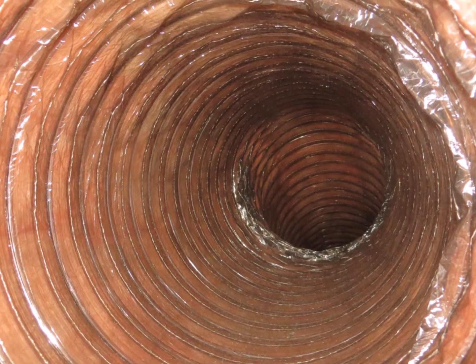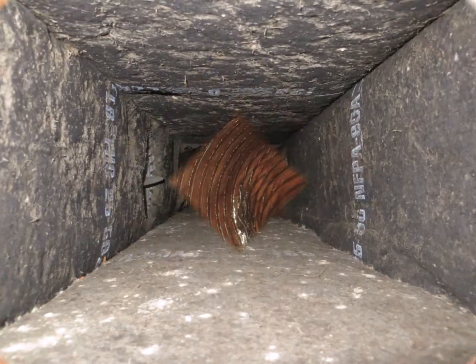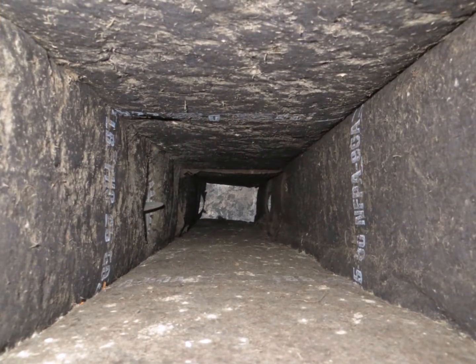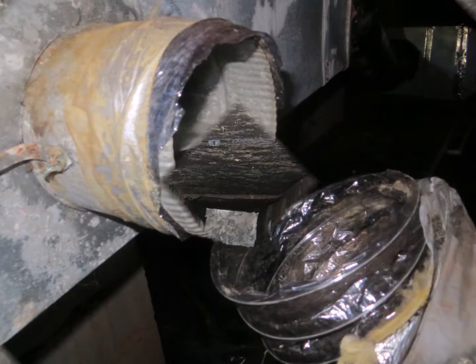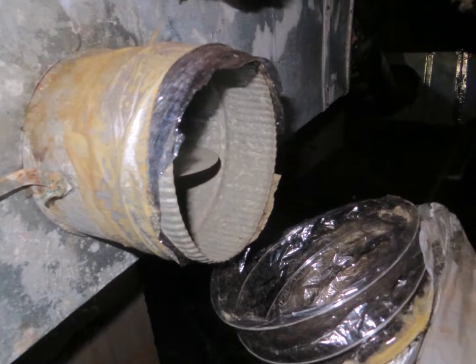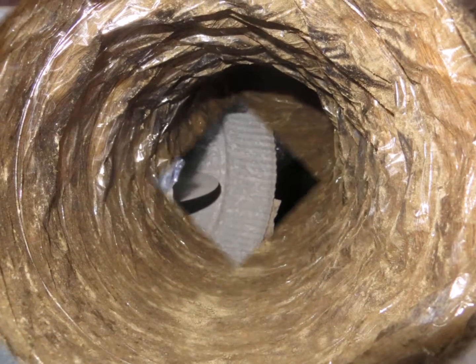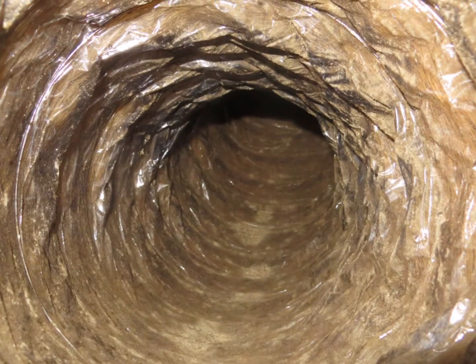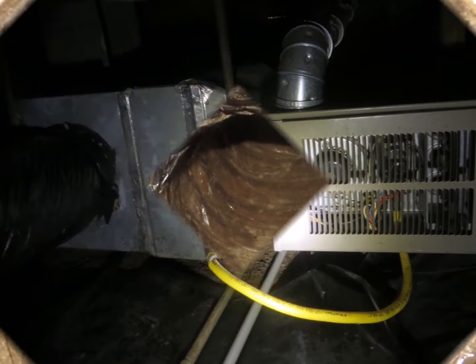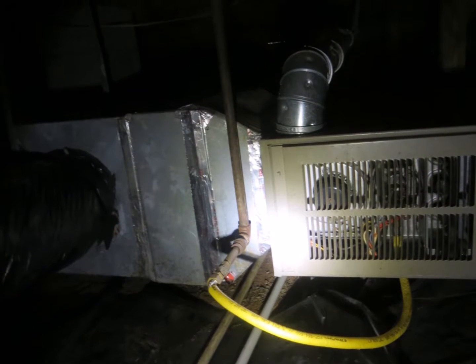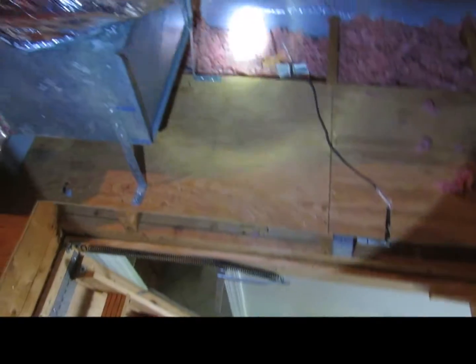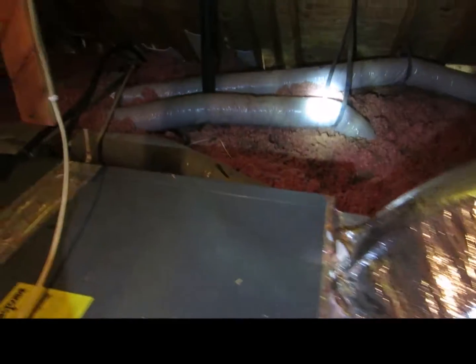The main trunk in the duct looked clean. However, the main trunk with duct liner showed extensive mold growth. Detaching a secondary flex duct from the main trunk shows extensive mold growth within the duct. The flex ducts should be replaced. The air handler that is currently there does not allow for this crawl space to be closed. Here in the attic, we have a need for an attic ladder cover. The insulation in the stairs is inadequate to stop the heat from penetrating into the living space.